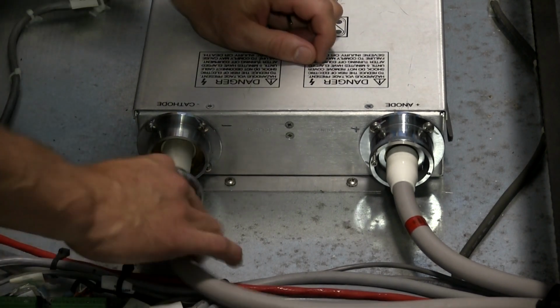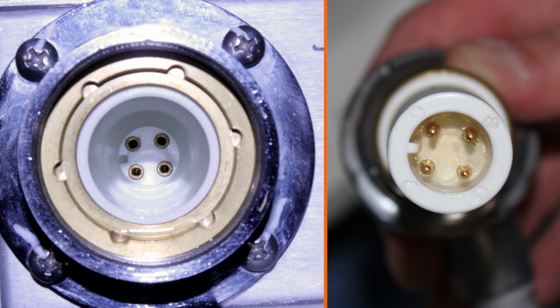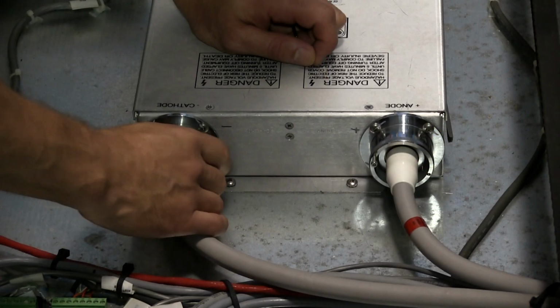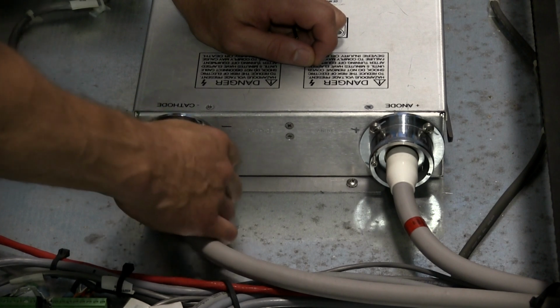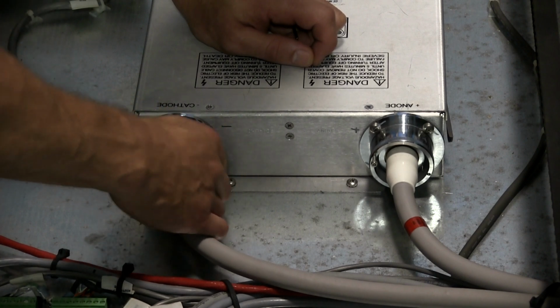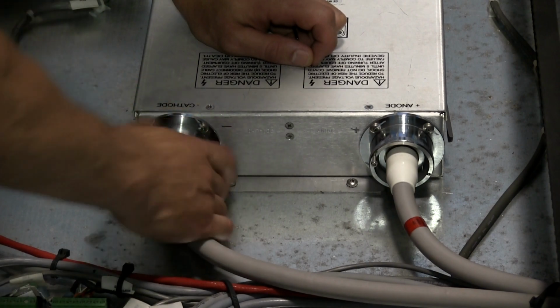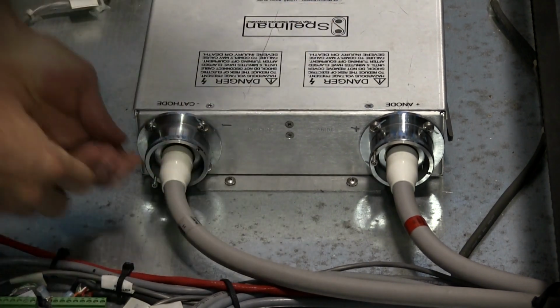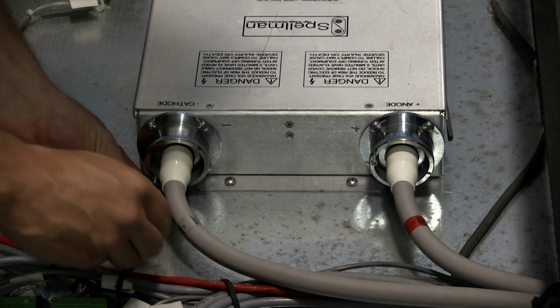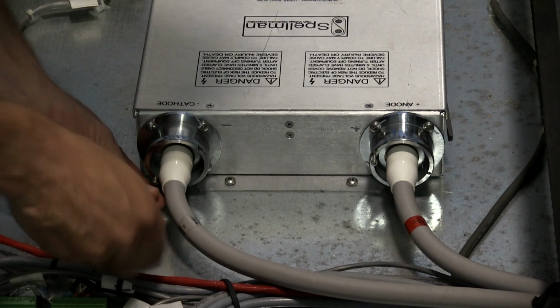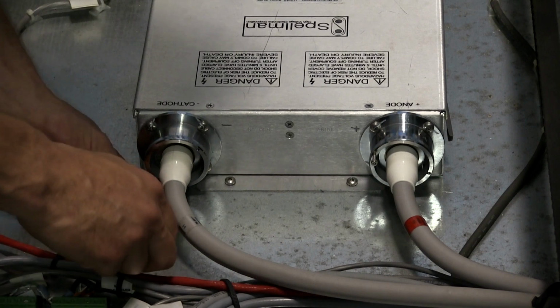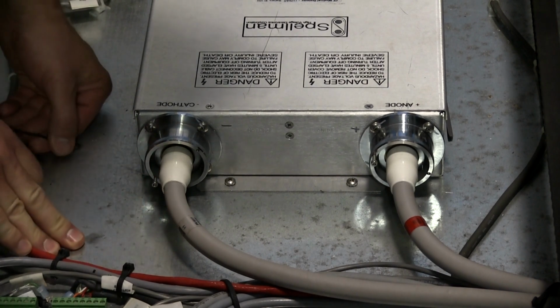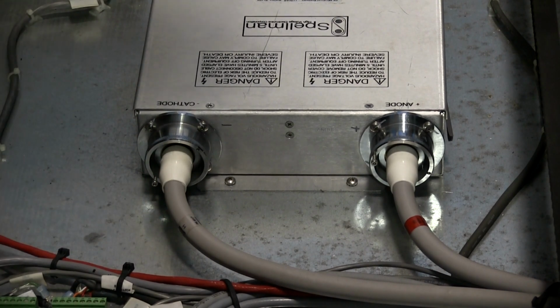Pushing in your connection, you want to make sure that your key slot is lined up properly so no damage to the prong occurs. Push all the way in, finish tightening down your high voltage connection, make sure to set your set screw, and continue this process for all connections of high voltage. After this is complete, reassemble your system and turn the power back on and boot up your PC.